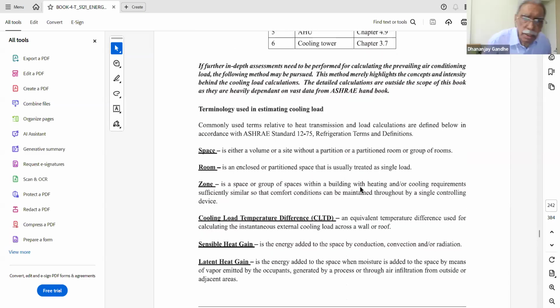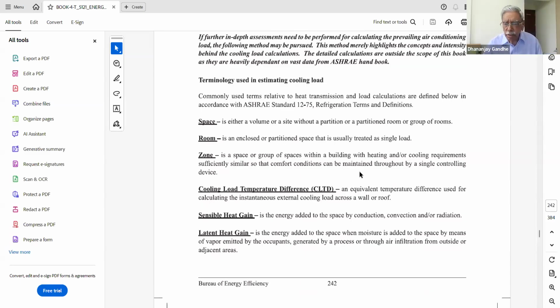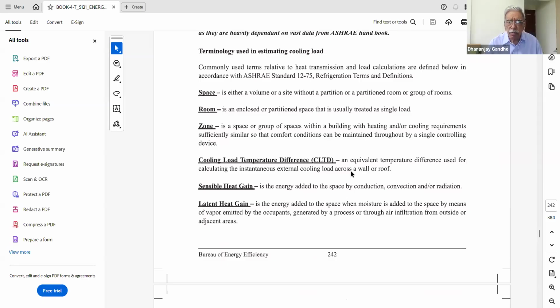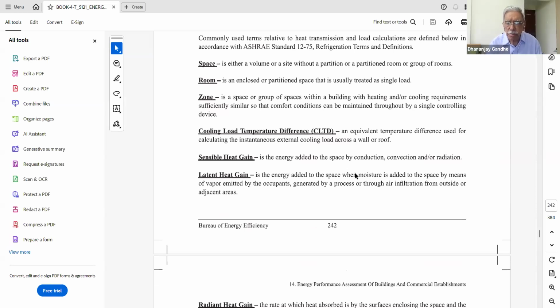For here, first let us see what are the terminologies used. I will not go further on space, room and zone; you all know about it. But there are certain terms which are often used in the calculation of heat load. One of them is the cooling load temperature difference, CLTD. That is equal to the temperature difference between the external cooling load and internal cooling load, either for a wall or a roof. So that defines the cooling load temperature difference for either a roof or a wall. The temperature difference is between outside and inside.